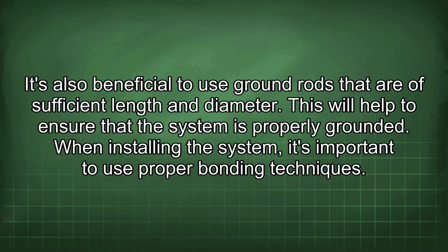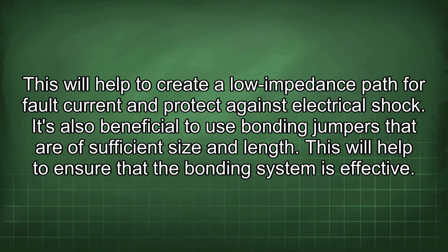When installing the system, it's important to use proper bonding techniques. This will help to create a low impedance path for fault current and protect against electrical shock. It's also beneficial to use bonding jumpers that are of sufficient size and length. This will help to ensure that the bonding system is effective.